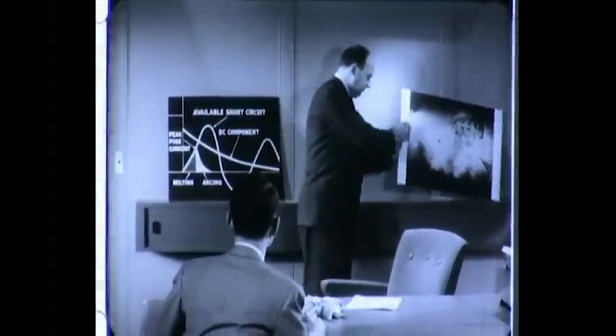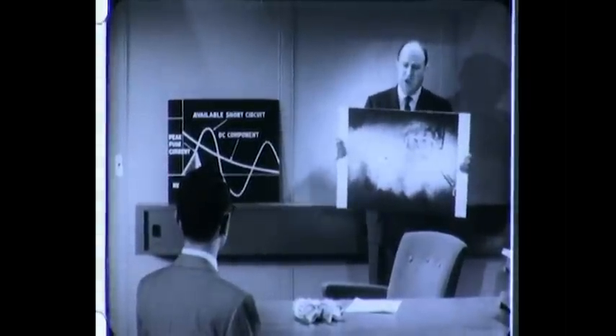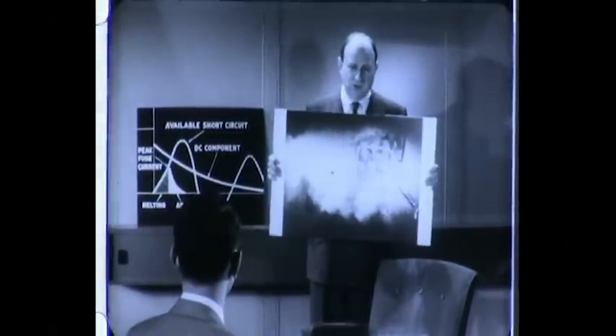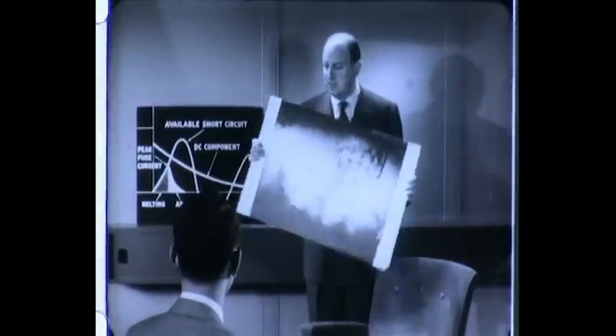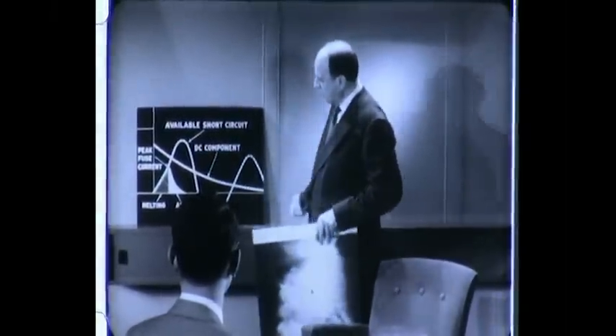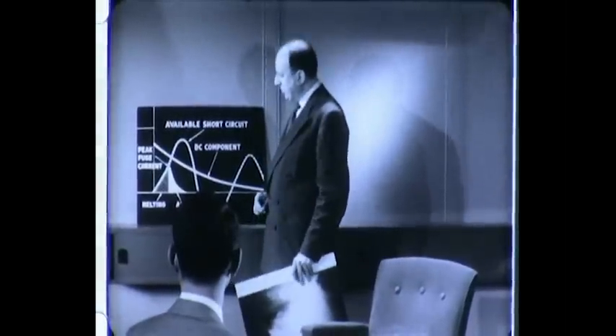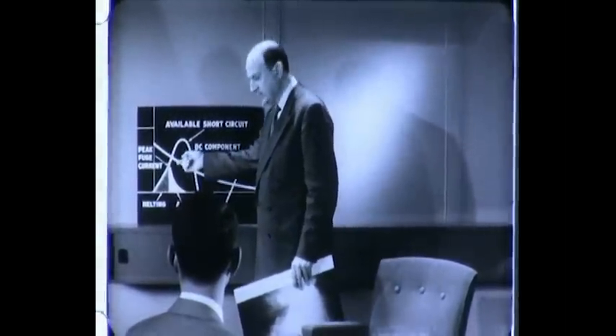Watch this, Cruncher. Boom. Now, that's a very good example, my boy, of what might happen when ordinary fuses are applied to circuits above 10,000 amps. The NEC fuse blew completely out of its holder, disintegrating and sending pieces flying way across the room. The CLF, however, remained in place. The CLF accomplishes its job long before the fault has a chance to reach its maximum potential. And you know what that means, don't you, lad?